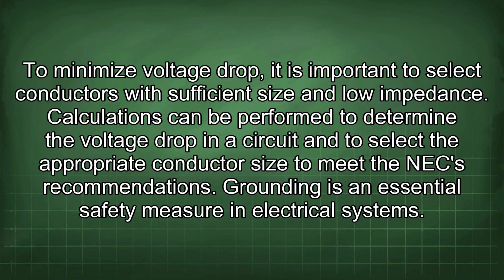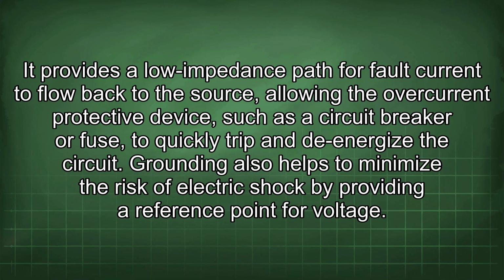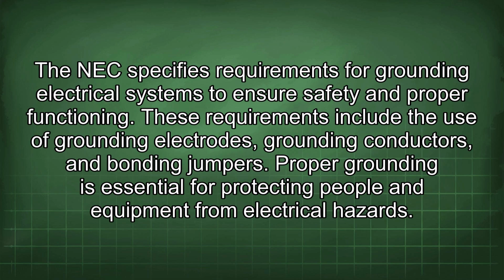meet the NEC recommendations. Grounding is an essential safety measure in electrical systems. It provides a low impedance path for fault current to flow back to the source, allowing the overcurrent protective device, such as a circuit breaker or fuse, to quickly trip and de-energize the circuit. Grounding also helps to minimize the risk of electric shock by providing a reference point for voltage. The NEC specifies requirements for grounding electrical systems to ensure safety and proper functioning. These requirements include the use of grounding electrodes, grounding conductors, and bonding jumpers. Proper grounding is essential for protecting people and equipment from electrical hazards.